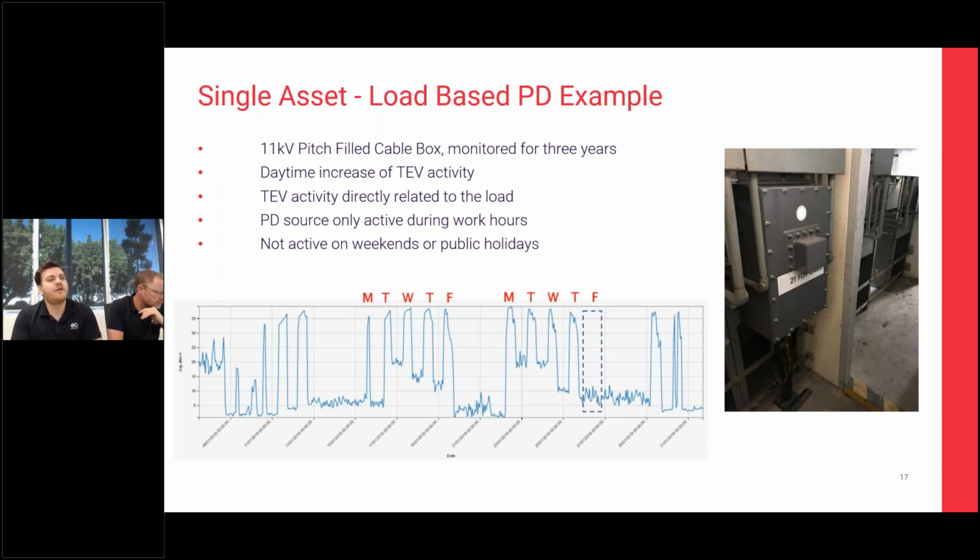What we were finding is that there was daily activity occurring, switching on and switching off with the load of that feeder. And as you can see from that picture, it was actually only active during daylight hours, Monday to Friday, switching off on weekends. But also, on the second Friday there was a public holiday in Australia and there was no load on the board. So this is just the type of testing where it can shift and it can go up and down.